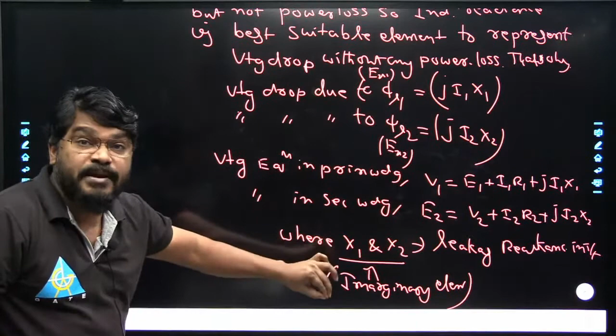So which is the suitable element to represent the voltage drop without any power loss? The inductive reactance element is the best suitable element to represent the voltage drop without any power loss. So that is what we conclude here. Leakage flux in the transformer creates some amount of voltage drop, but not power loss. The inductive reactance is the best suitable element to represent voltage drop.